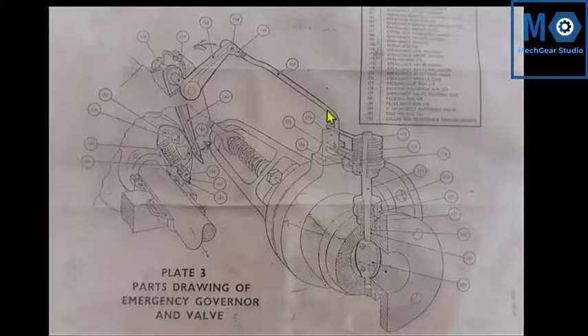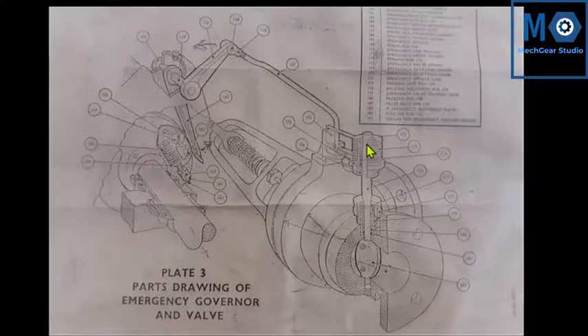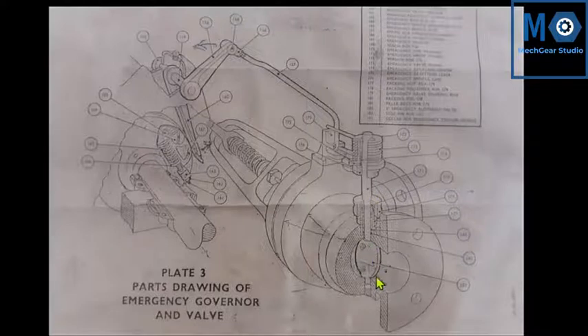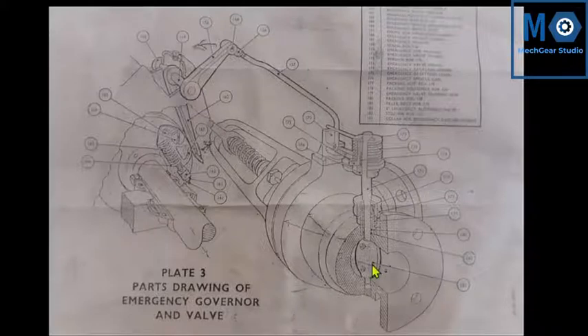At this pin point it is going anticlockwise because it is on this smaller shaft, and this external lever — I have shown this lever externally — is going also anticlockwise because both are on the same shaft. So when it is going anticlockwise, this bar will be pulled towards upside, removing this spring from the lock position, and also removing the lock pin. At the bottom, one lever is provided — I have shown this clearly. This movement removes the lock of the spring, and due to the torsion of the spring, this shaft will be rotated.